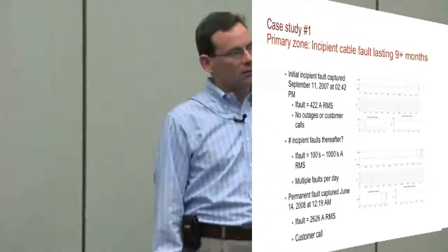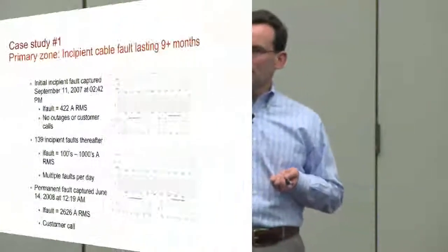In between September 11, 2007 and June 14th, anyone want to guess how many other incipient fault cases we got? How many we saw? 139 detected - you can see short-lived, high-magnitude faults that cleared themselves because there was not a single OMS record, not a single phone call. And then it finally failed at over 2,600 amps.